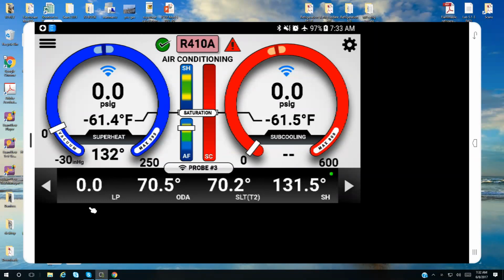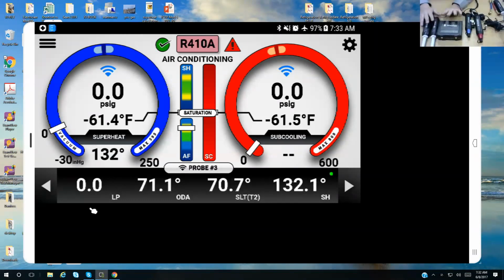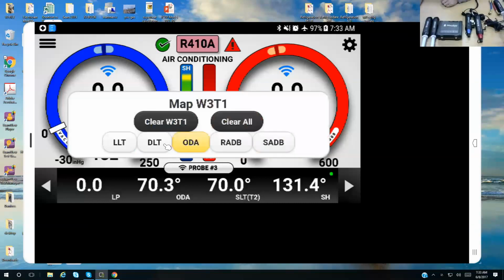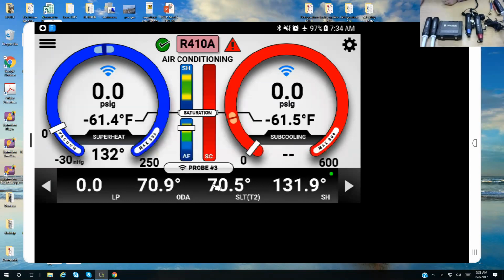All right, so here we have probe 3, which is the low pressure probe. Again, if I wanted to change that temperature, if I decided I did want to hook it up to the discharge line or the liquid line, you can do it right from this screen. I'm going to keep it as the outdoor air, but this just shows you how user friendly it is. We can make changes from multiple areas just by tapping on things. And then here's probe 4.